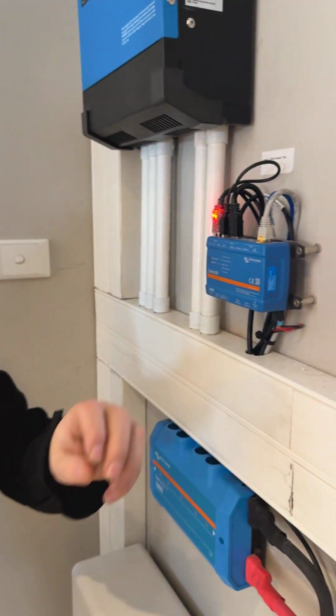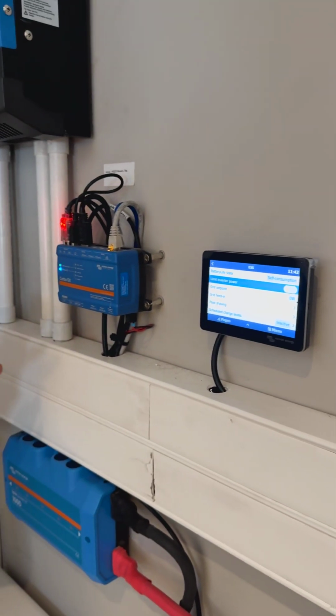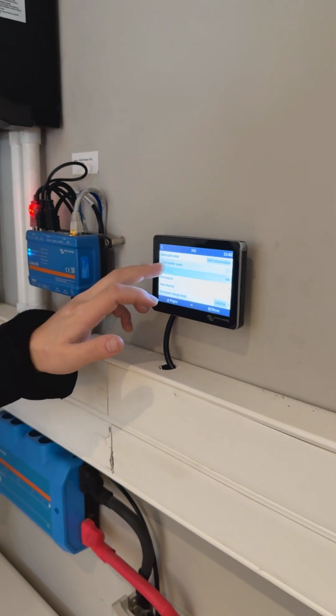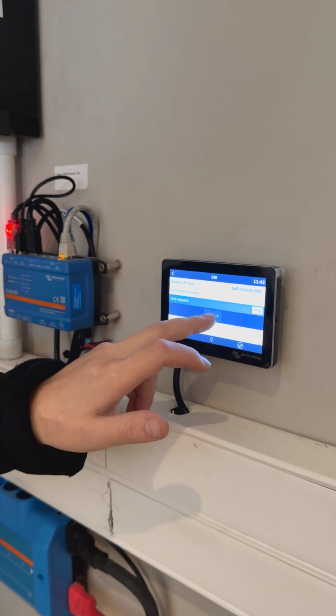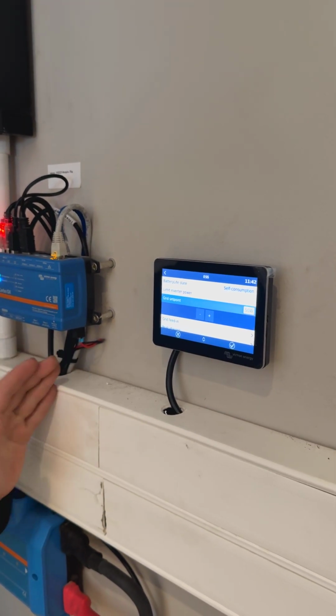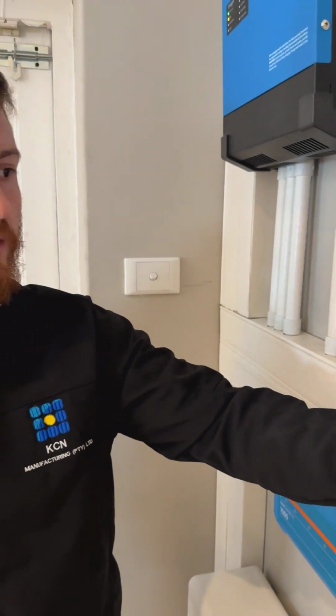Power cannot sit still, and the energy meter tries to measure that as quickly as possible. So the set point is just a reference of keep it as close to 0 as possible. In most cases, when we do our setups, we'll keep it at 50 or 100 depending on the prepaid meter. Some of the older prepaid meters do not like when there's even a drop of feedback on it. So we'll set our grid set point higher, between 50 or 100, so that when there's a heavy load and the load falls away, it stays far away from 0 or into the minus figures.